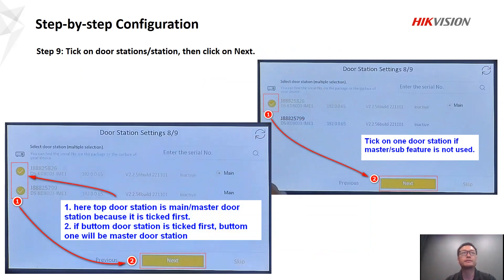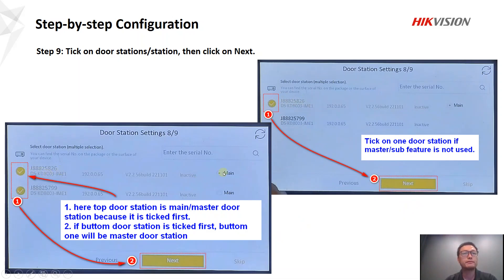In step nine, this is very important. If you have one door station, simply click on it and click next — it will be very easy. If you use two door stations and want to use the master and sub door station feature, pay attention: the first door station you click on becomes the master door station. So if you click the bottom one first, then the top one, the bottom one will be the master door station. This is very important. After clicking, click next.